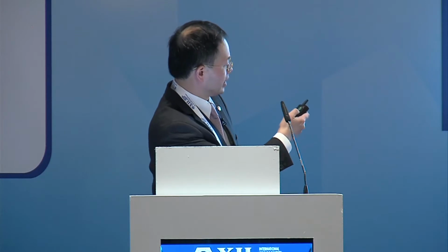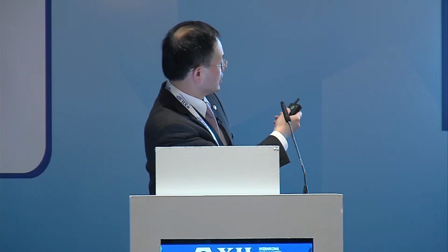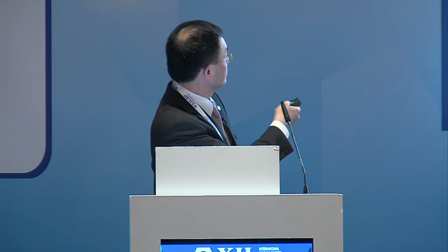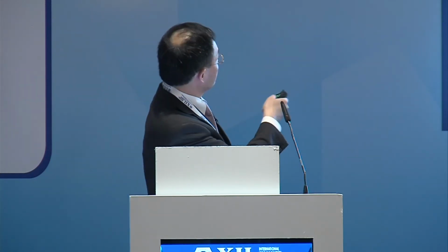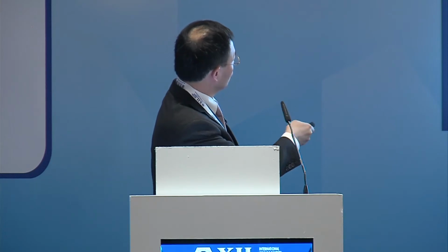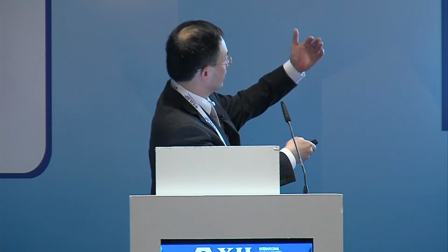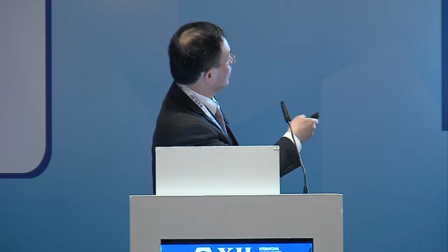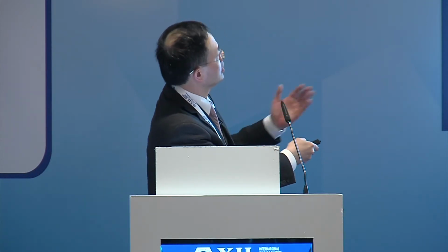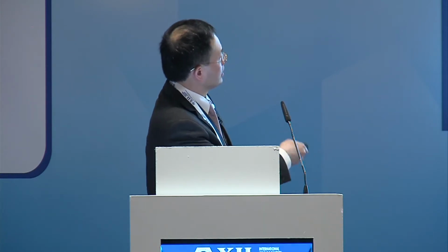In the US, as we mentioned earlier, we have the AIA FGI standard. We have ASHRAE. We also have CDC. We have VA and many others. And we put this into the same chart as a quick comparison: operating room, isolation room, and for isolation room the anteroom, they are independent categories. Total air change per hour requirement, the minimum outside air change, outside air in the total air. So this is the summary chart, and this also is the pressure relationship.